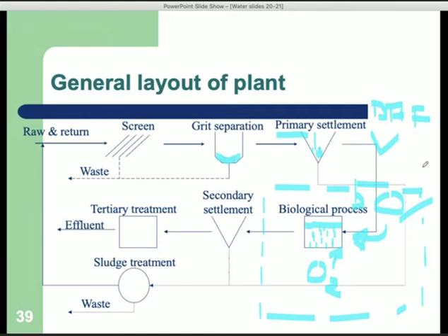Yes. So into the biological treatment plant goes the BOD. Into the biological treatment plant goes the oxygen, but out goes nothing but clean water. So you're using up the BOD, and you're using up the oxygen that gets emitted as carbon dioxide, and you're also growing bacteria. And these bacteria you do not want to get into the environment, so you have the secondary settlement where the bacteria settle at the bottom. What overflows is then the treated water.